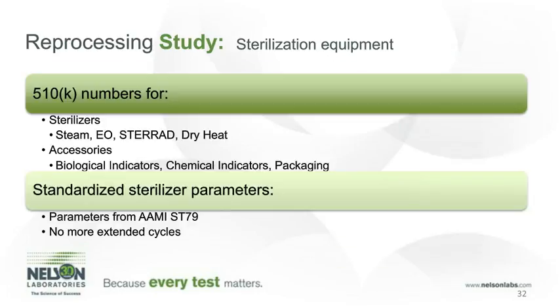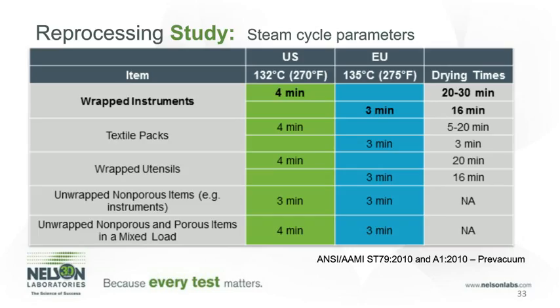FDA also requires 510K numbers to be utilized for sterilizers and all accessories, including the biological indicators, chemical indicators, and packaging, and that standardized sterilizer parameters are utilized, and no more extended cycles are performed. The parameters for these can be found in AAMI ST79, TIR 12, and the new FDA guidance document. Here is an example of what those standard cycles look like.